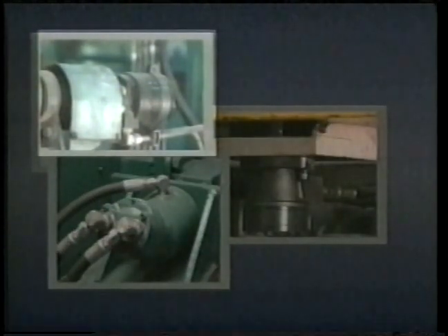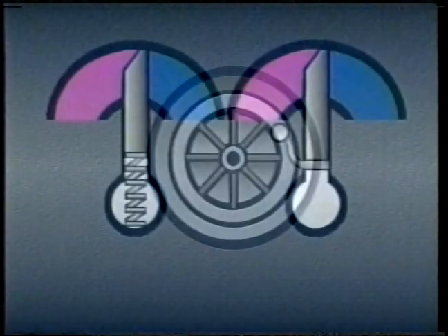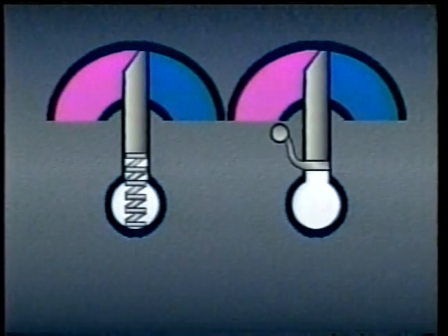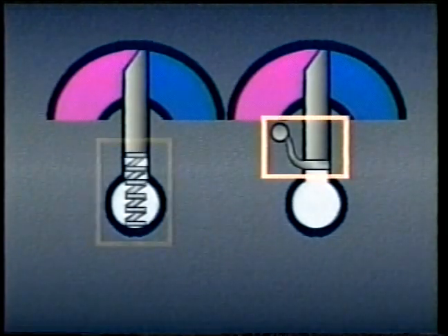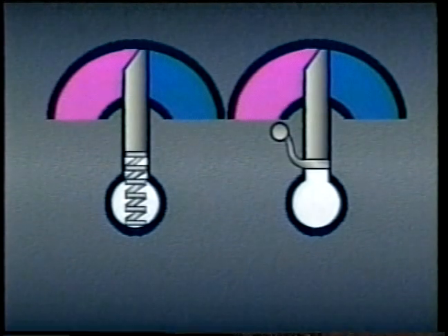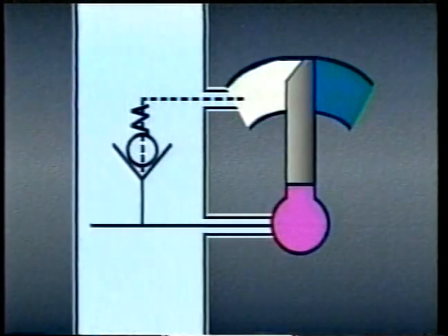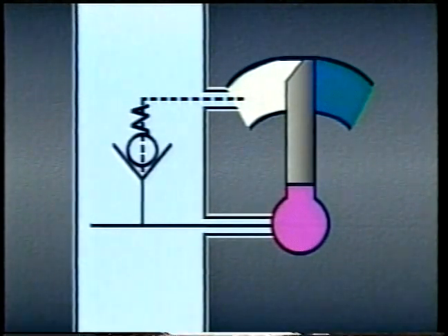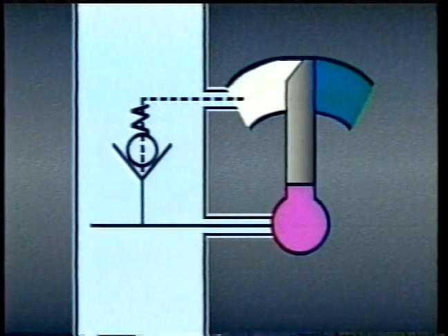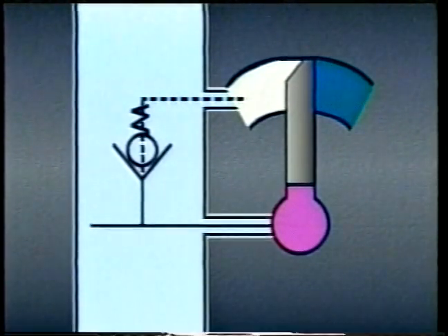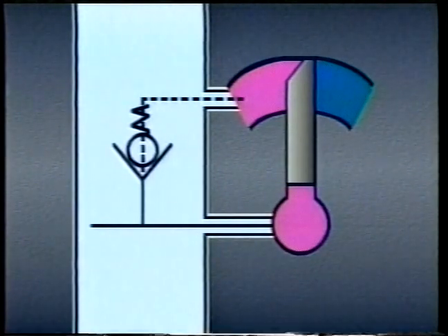In a vane motor, the motor won't turn until there is a seal between the vane and the cam ring. That means that centrifugal force cannot be used to force the vanes out to the cam ring at startup. In some vane motors, springs are used to hold the vane against the cam ring. This can be done with a coil spring or with a spring attached to a post. In either case, once the motor is turning, fluid pressure is directed to the underside of the vane to help maintain a tight seal. Fluid pressure may also be used to force the vane out before the motor starts. This is done by using a check valve, which prevents fluid from entering the motor inlet until pressure is high enough to force the vane out against the cam ring.